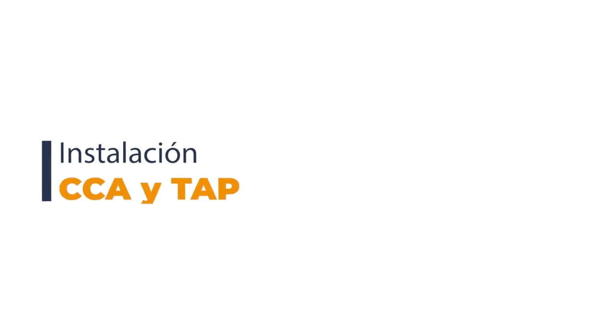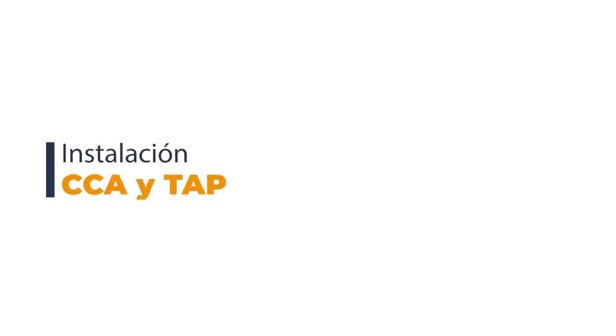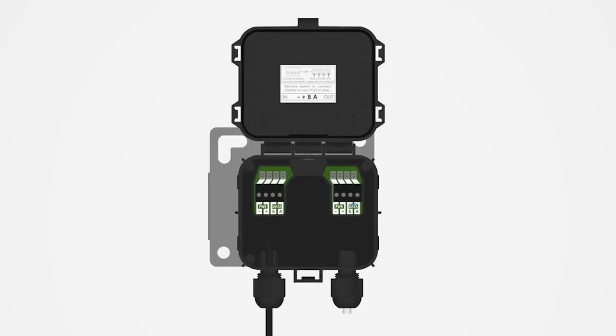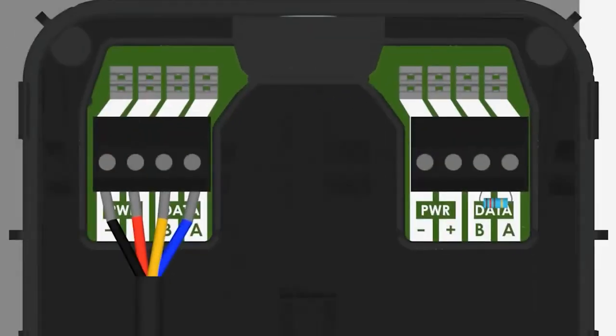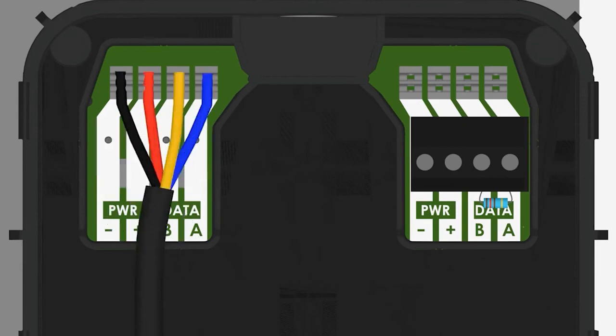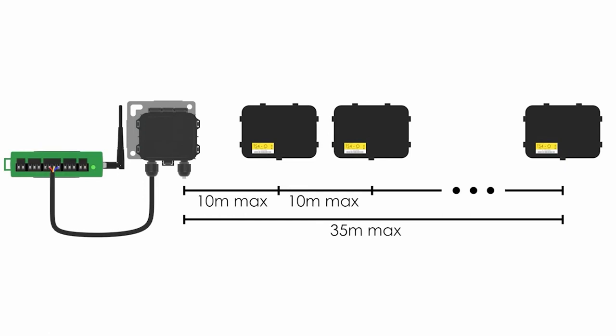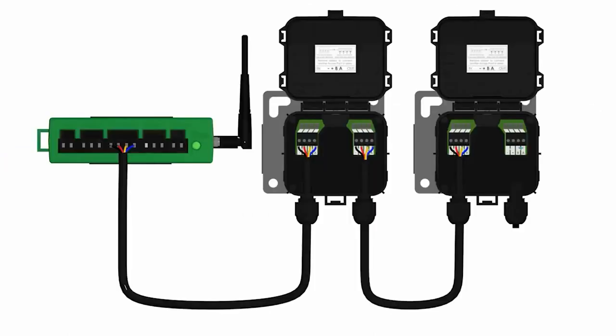How to install the CCA and TAP? The TAP is easily mounted on a module frame without tools, and the compartment is easy to install. The CCA should be installed on a module. Place the TAP within 10 meters of any TS4 unit in the array, with a maximum distance of 10 meters between TS4 units and 35 meters from the TAP to the farthest TS4. All TS4 units in the system must be within range of a TAP for monitoring and security capability. The CCA should be in a convenient location, close to the inverter and with AC power and internet access.